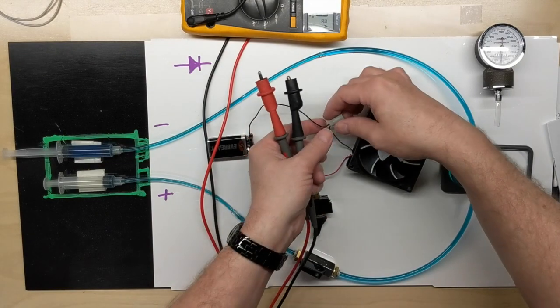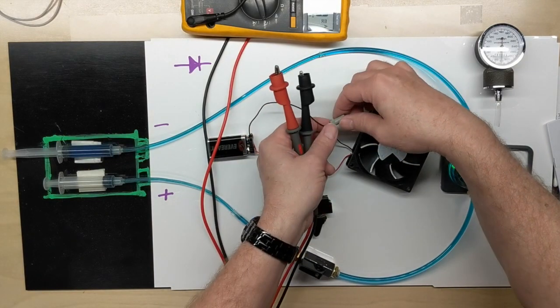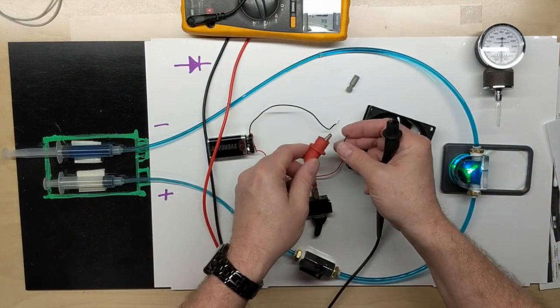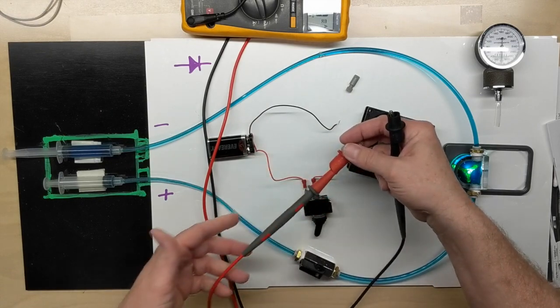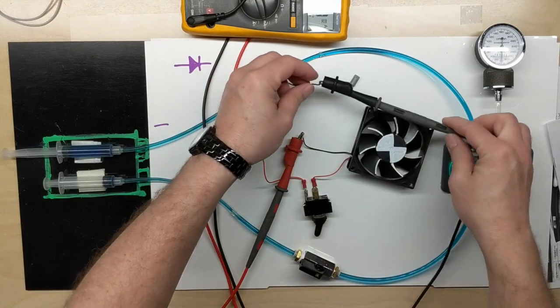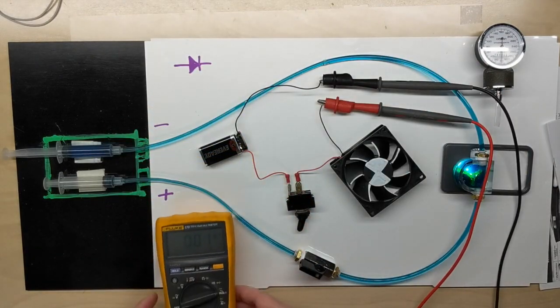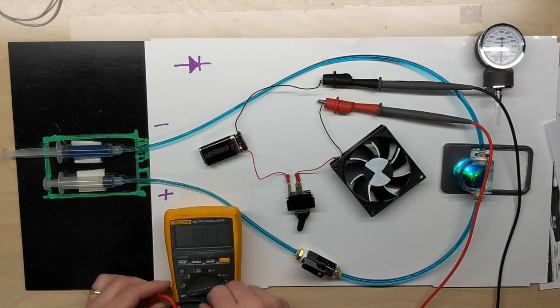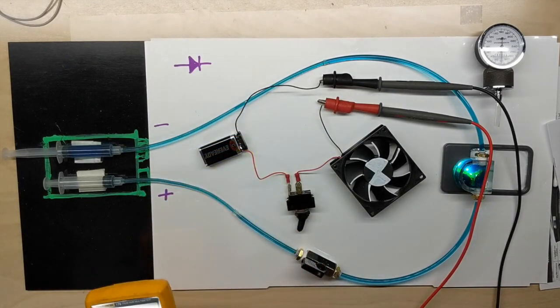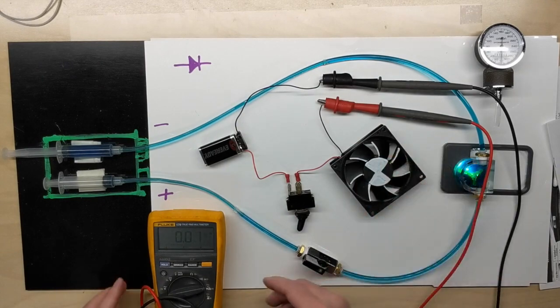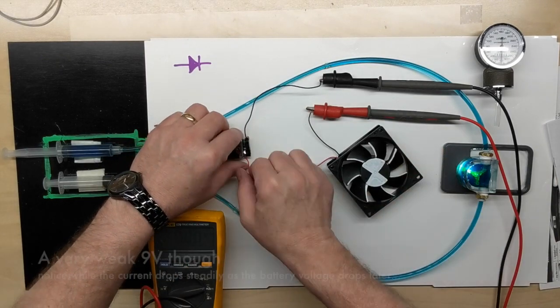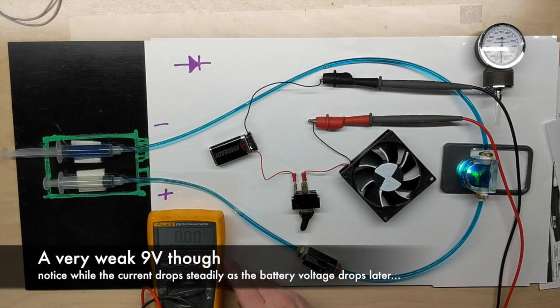So we can do this more than one way. We can break the circuit here and put the meter across here. This is the more positive side, so I'm going to put the red lead or the positive lead. This is the one going back to the negative post, I put the negative lead on. I'm going to move the meter here so you can see it a little bit better. So I have my leads on common and 400 milliamp range because I know this fan's in the milliamp according to its data plate. At 12 volts DC, which we're putting nine across.